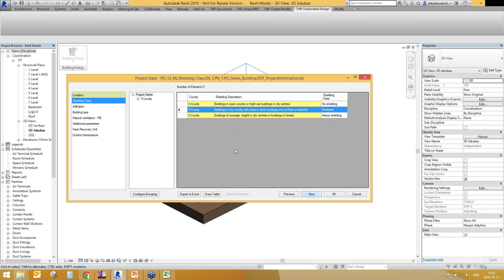If we have a low tightness building, we will get the infiltration air change of 0.42, but in some reasons we have added the design air change when there's a difference between inside and outside of 50 pascals, and we will get six times changed air inside the building using such a value. So we can find needed parameters here.